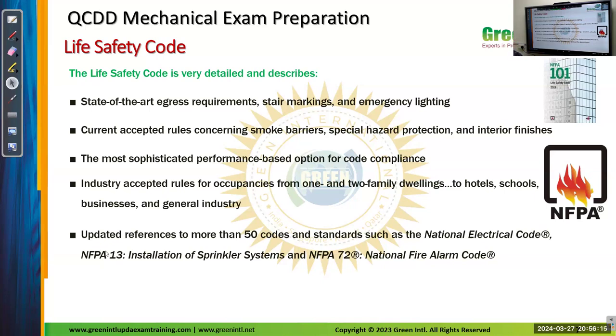So, the current accepted rules concerning smoke barriers, special hazard protection, and interior finishes, and the most sophisticated performance-based option for code compliance. The industry-accepted rules for occupancies range from one and two family dwellings to hotels, schools, business, and general industry. Egress, there are many questions from egress. Yes, NFPA 101, the main questions will come from egress, illumination, and the height, the barrier, those details.